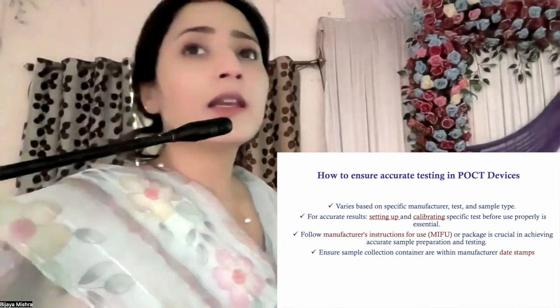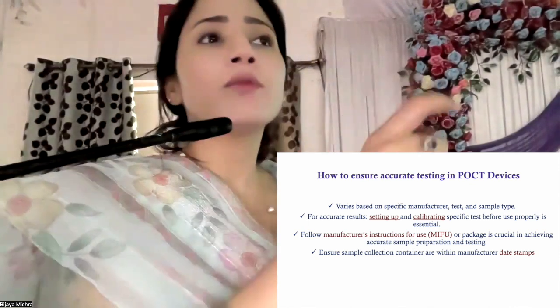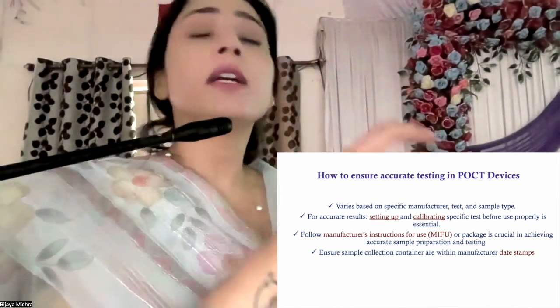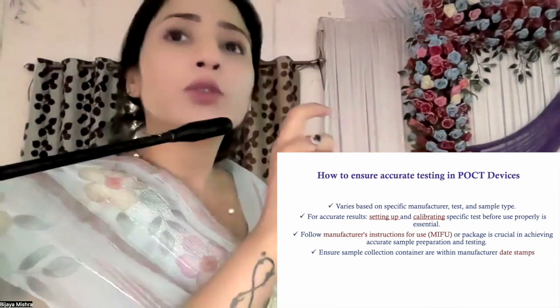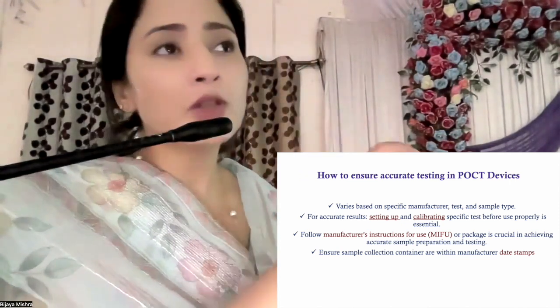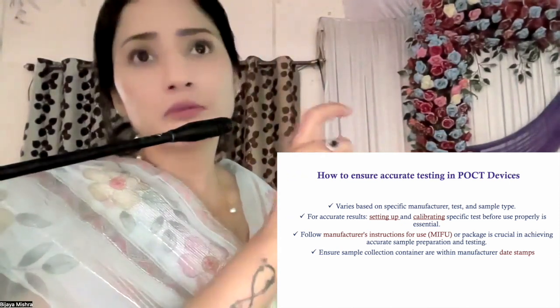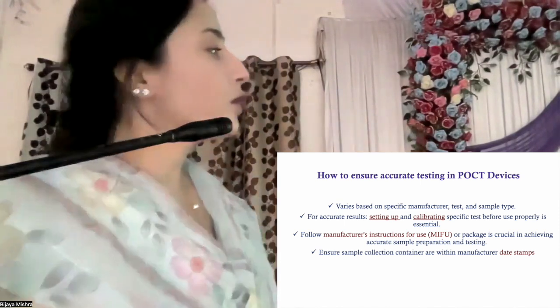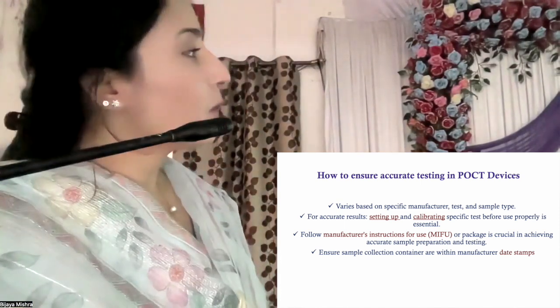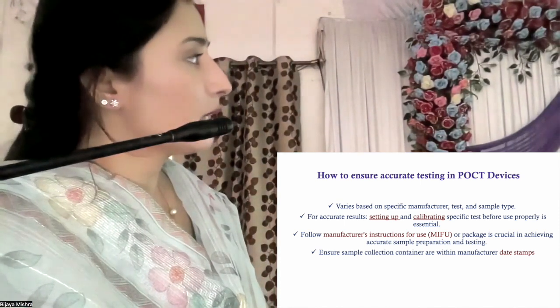And finally, whatever strip or cartridge we are using, we need to check the date stamps, and we should make sure that expired cartridges or reagents are not used. In this way, we can ensure accuracy of the overall point of care testing device.